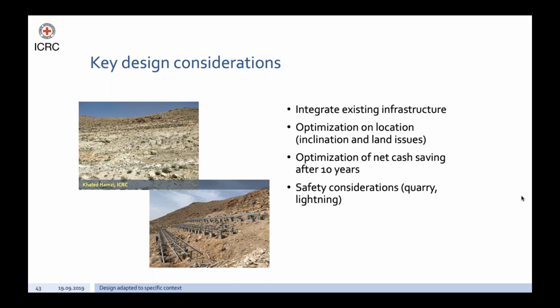Taking into consideration irradiation data for summer and winter, we optimized the inclination. I will come back on this. Finally, the whole system is optimized for net cash saving after 10 years. While a bigger system size would allow us to operate for a longer time per day, it also means increased system cost. The system size was defined by optimizing the net cash saving after 10 years. This took also into consideration the cost of electricity from the grid and the operating cost of the backup generators in the time slots where the solar system is not the primary source of power.